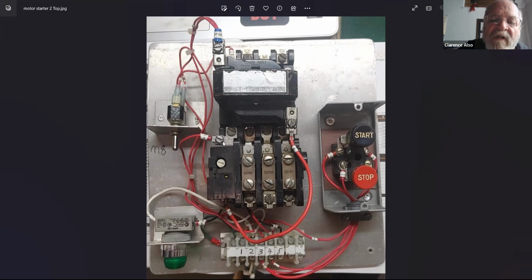That's the other contact that is going to close whenever that armature pulls down on the coil. That's going to close, just like it's going to close for the 3 phases going to the motor. When that closes like that, it reports back to your circuit that we have closed the contact, and when that contact closes, it's going to close around that start button.